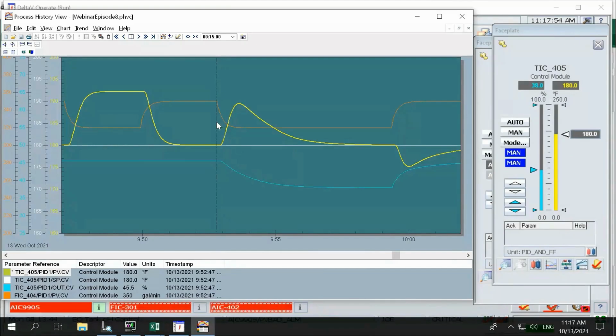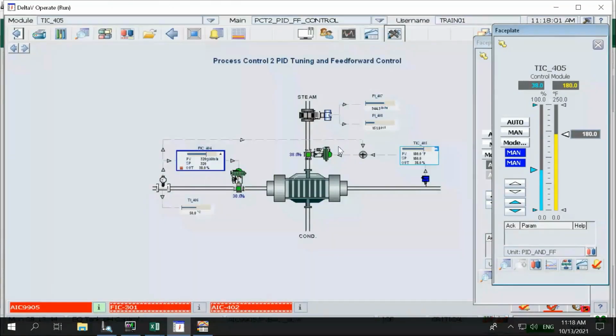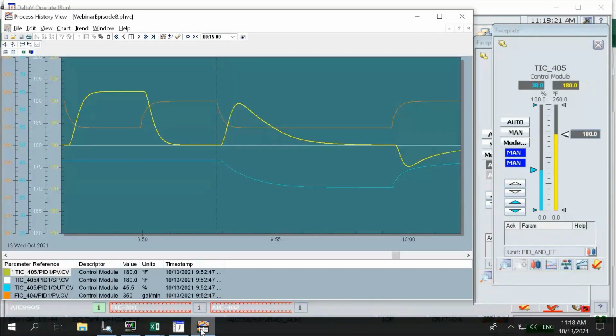One thing to understand is that in this temperature process, I built in about 8 seconds of time delay between the moment I make a change on the steam valve and the moment I actually perceive a change in temperature. It could come from low heat transfer dynamics and transportation dynamics. So I have 8 seconds of time delay. I did the load disturbance, but the temperature only started to change 8 seconds later, and my PID controller alone, with no feed forward, only started to react then. So you have to understand I'm actually 8 seconds behind, or whatever the process dead time would be.